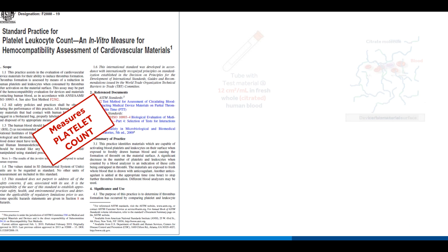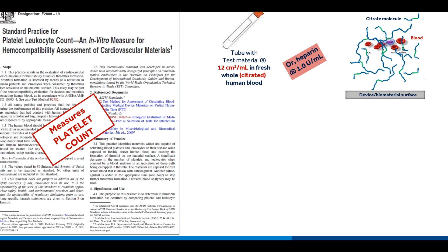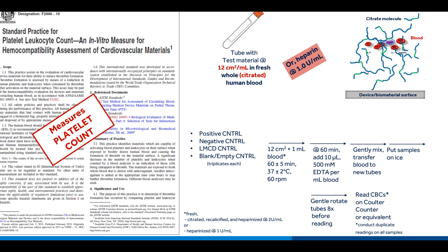And this test is also incredibly simple, but here it actually calls for 12 square centimeters of test material per mL of blood, and it calls for, again, using citrated human blood. And in the recent edition, they've added the opportunity to use heparin instead of citrated blood, which is a huge improvement. But again, the layout is similar with the various controls. And in the end, the counts are done with a standard Coulter counter. The problem with this test, and it's kind of illustrated in this schematic, is for a simple device like a stent that adds about a half a square centimeter to a square centimeter, that gets exposed to the whole body volume of blood in an adult, which is about 5,000 milliliters.